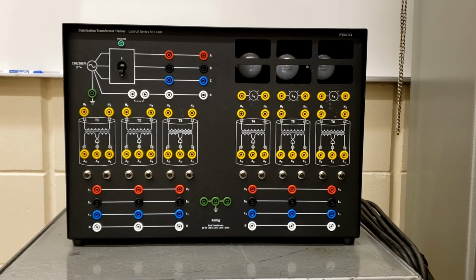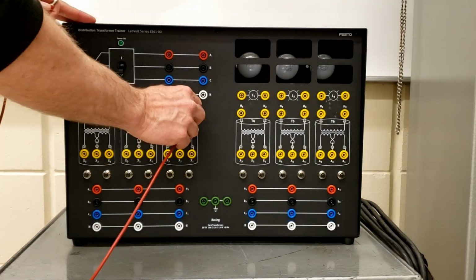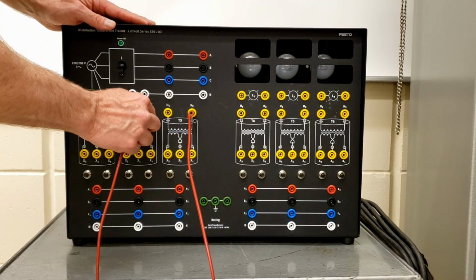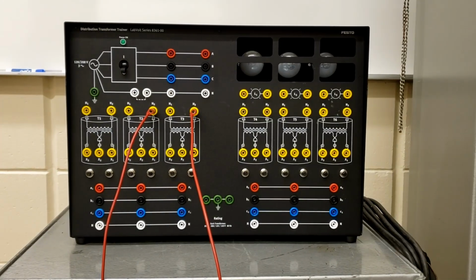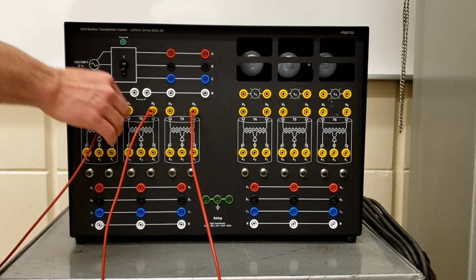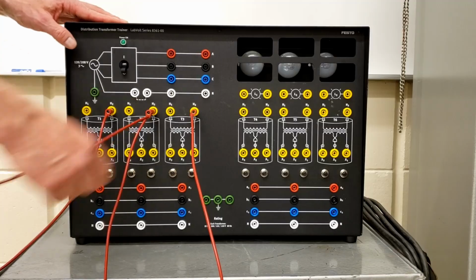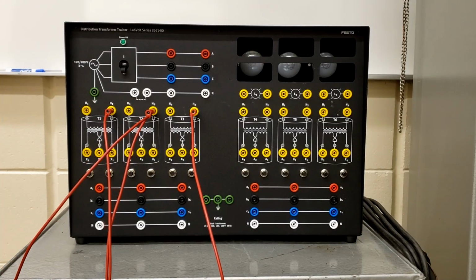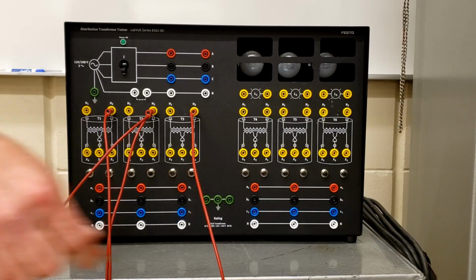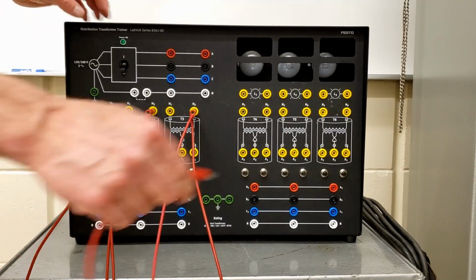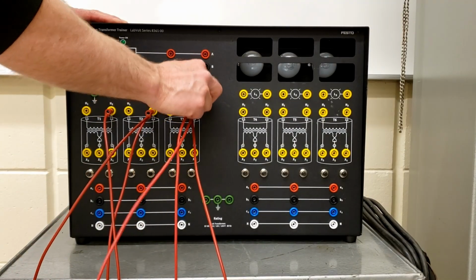So for that, it looks like we have all the H2s tied together. Let's start off with that. So all the H2s are going to be tied together. And then this is the grounded primary, right? So all of them are going to be tied together, and you'll notice that H2 of transformer 2 is bonded to the neutral. Okay, so that's going to the neutral.